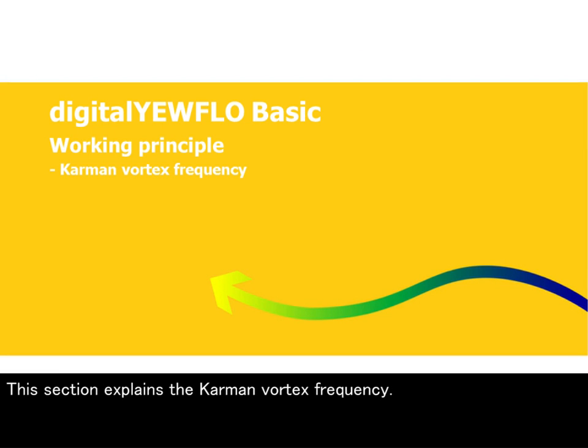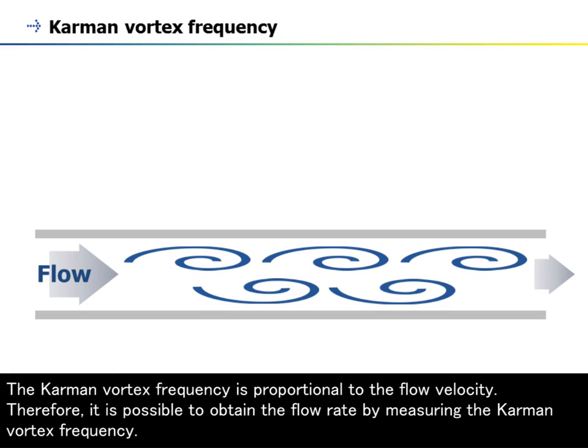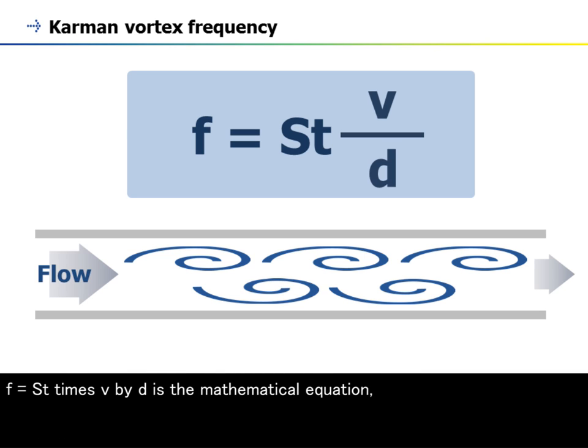The Karman vortex frequency is proportional to the flow velocity. Therefore, it is possible to obtain the flow rate by measuring the Karman vortex frequency. f equals St times v by d is the mathematical equation.